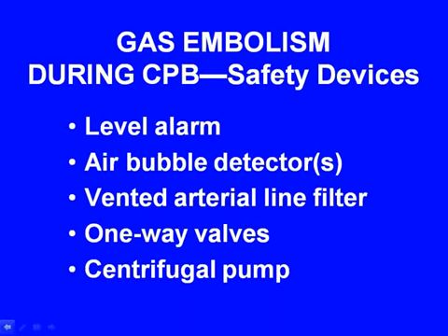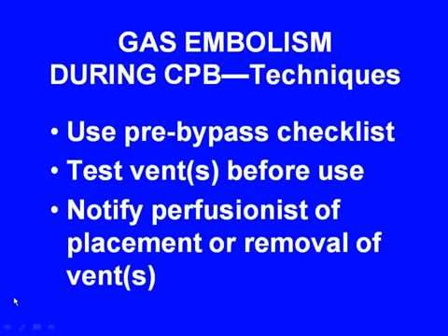Vented arterial line filter, of course, has been talked about and studied for many, many years. One-way valves, either after the centrifugal pump or on smaller lines, are effective to prevent air embolism, and use of a centrifugal pump can prevent pumping of massive air embolism.